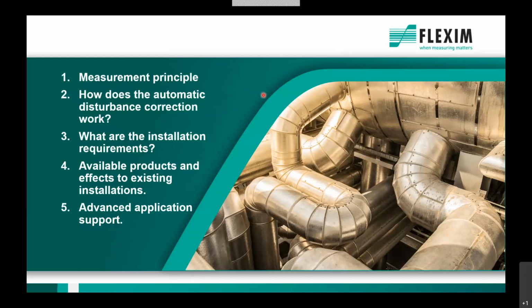We will start with the measurement principle to tell you where the disturbance influence actually comes from and how it affects our flow reading. We will talk about how the automatic disturbance correction works in the following slides, what is required for installation, what available products I basically have, what I can do with existing products, and how I can benefit from that function. And in the end, I will give some advice to help analyze the measurement deviation you may face in the field when you do measurements. So how does this disturbance correction actually help us to give a better analysis of our measured data?